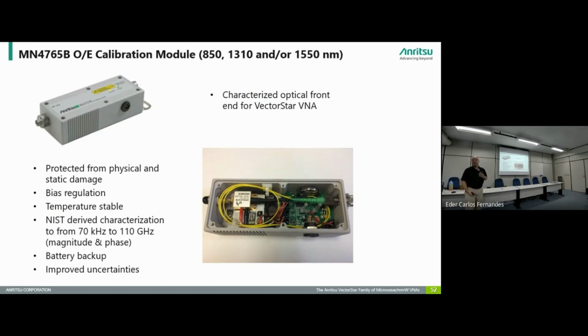So it makes it a much more flexible measurement solution for this application. But what's unique about this module is that it's got the photodiode on a temperature oven, kind of a temperature stabilization. And then over here on the right side is the voltage regulator that keeps the bias regulation. So we have bias regulation, temperature stability, very important. And we have everything packaged inside.